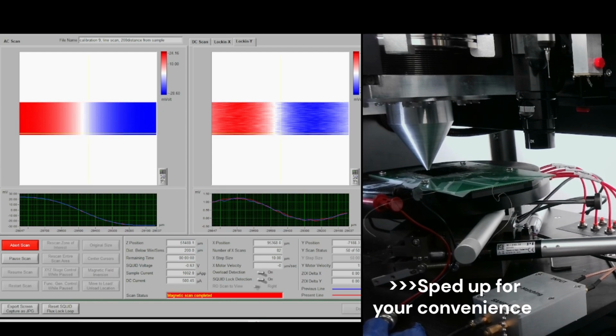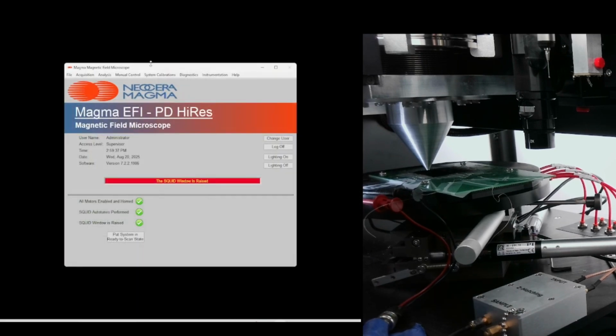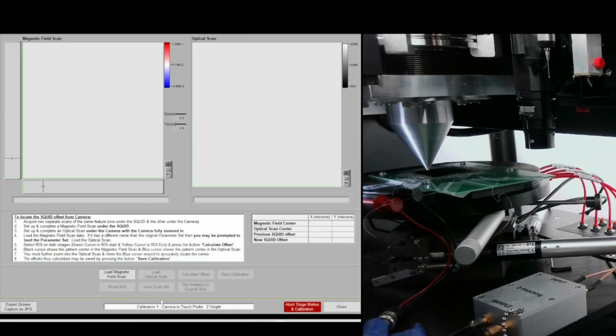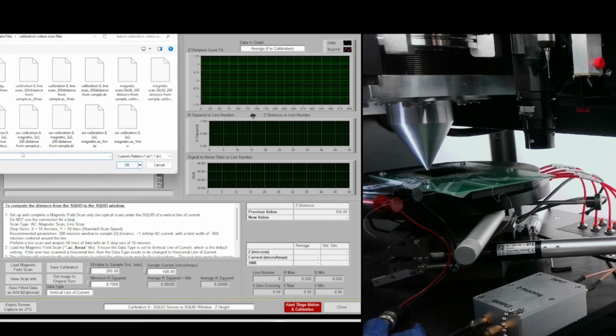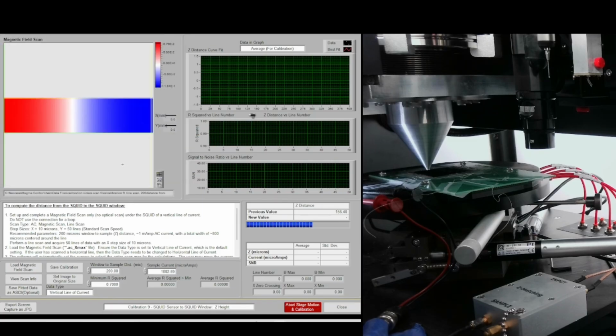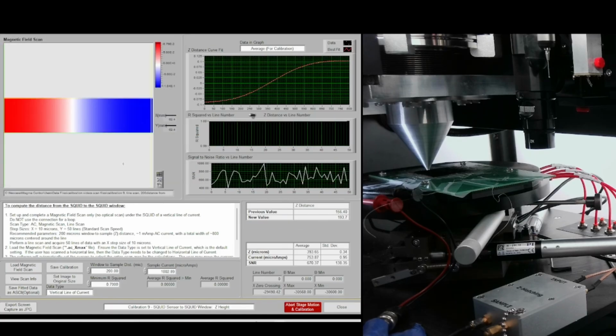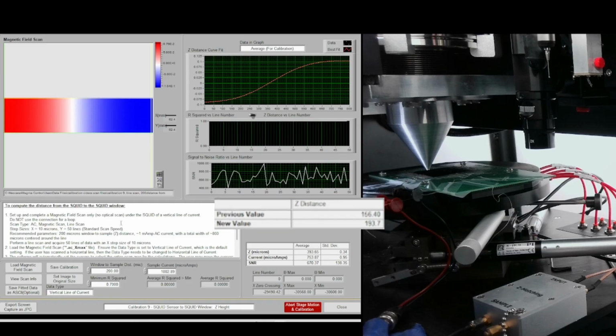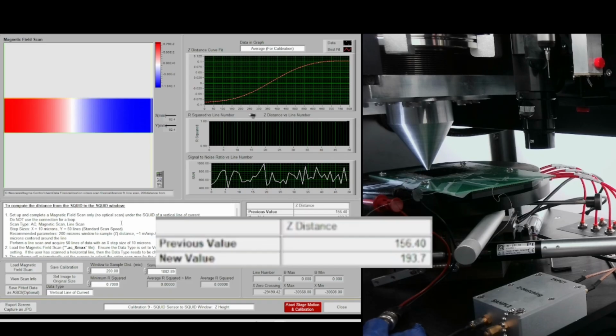Once the scan finishes, we click Done and head to System Calibrations, opening the tab for Calibration 9. We click on Load Magnetic Field Scan, and from the files, we select the X-direction scan file only. After loading the scan, we check the Z distance box. It's located in the middle right of the screen. The value here must be 200 microns or less to pass the calibration.